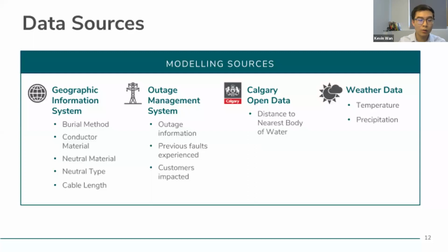And so starting with our GIS asset record management system, this is where we had all of the physical attributes of underground cables, maintained by the GeoWarn group and stored in a central system. These include physical attributes such as burial method, conductor material, neutral material and type, and also cable length for each cable. So this is all the data we're combining, together with the outage management system, where we are able to understand the history of outages on these cables, number of previous faults experienced, and customers impacted, which also provides more information on the loading.